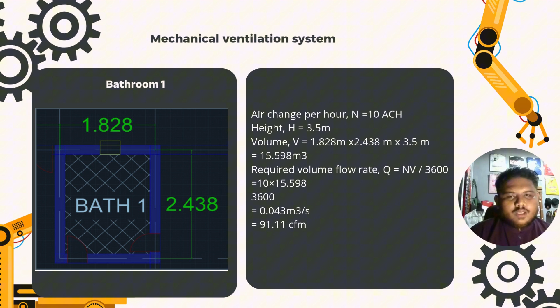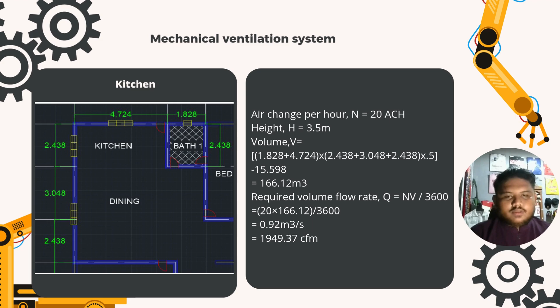Second, the kitchen. Air change per hour equals 20 ACH. Height is 3.5 meters and the volume we get is 166.12 cubic meters. Required volume flow rate Q, we get 0.92 cubic meters per second, and we must convert to CFM, so we get 1949.37 CFM.